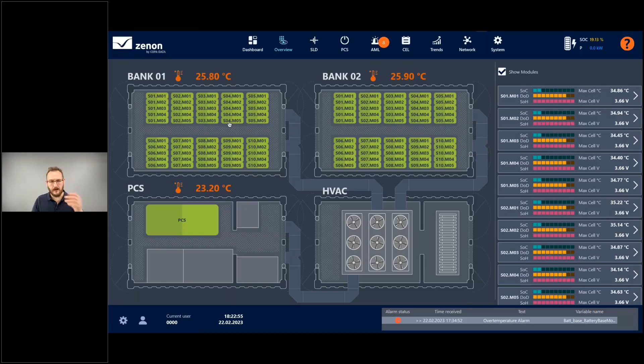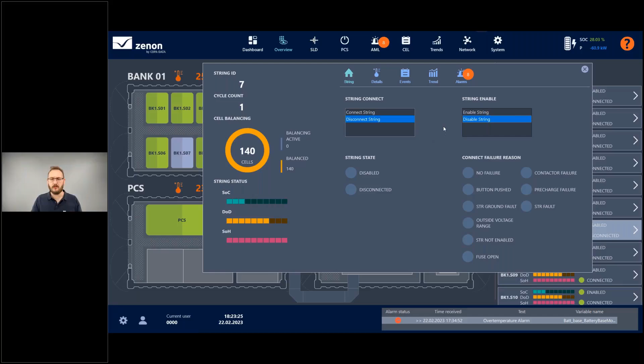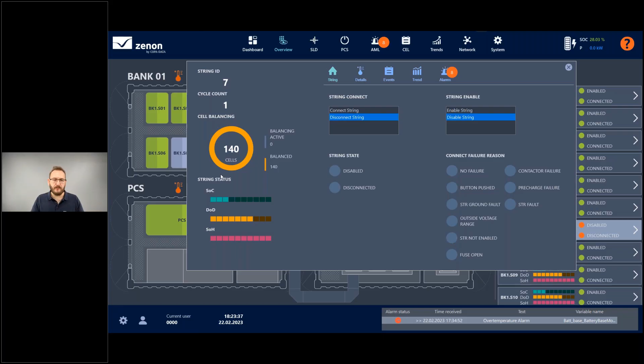Let's say I've done some investigation and I'd like to take this particular string out of commission. We can do this by mechanically disconnecting the string, but also, from a SCADA or HMI point of view, disabling it from the battery management system. We would send a signal to the BMS, which would then decommission this section of bank 1.